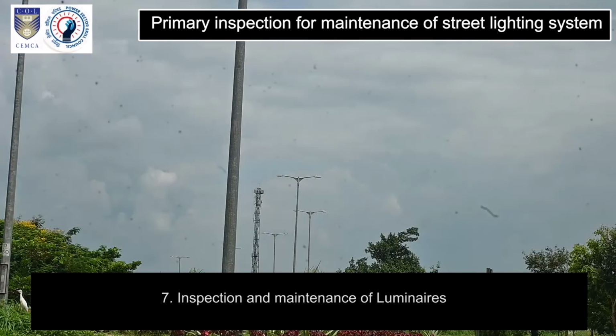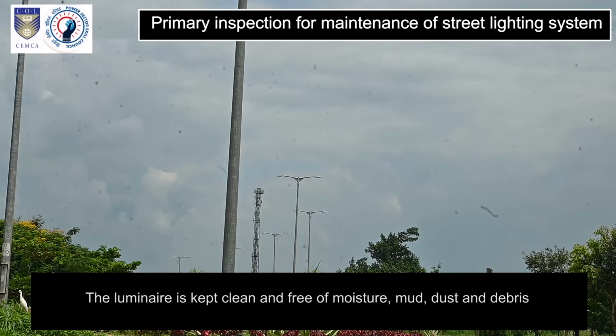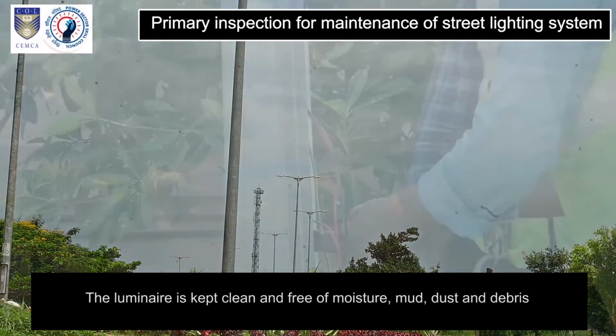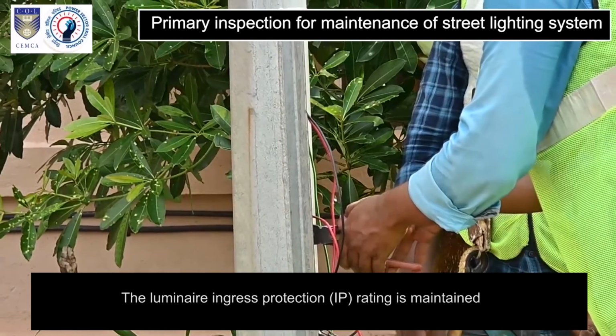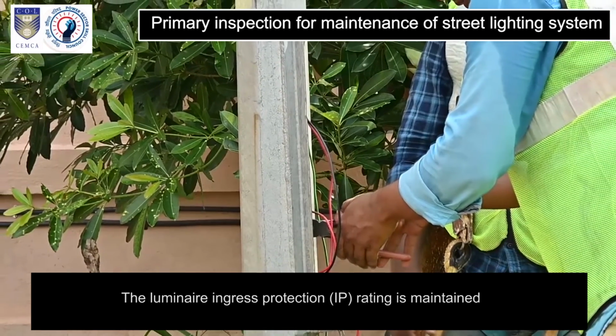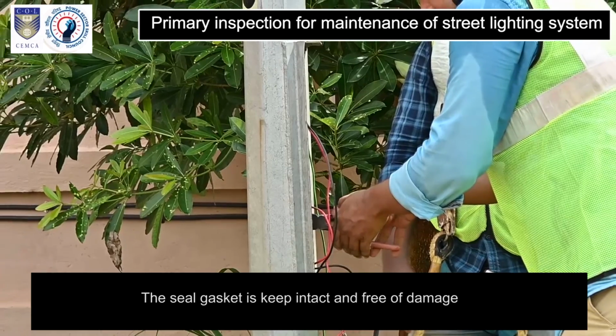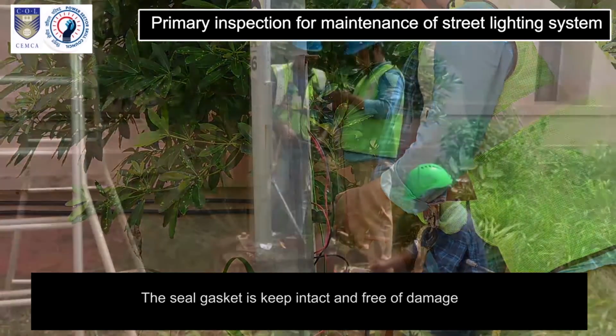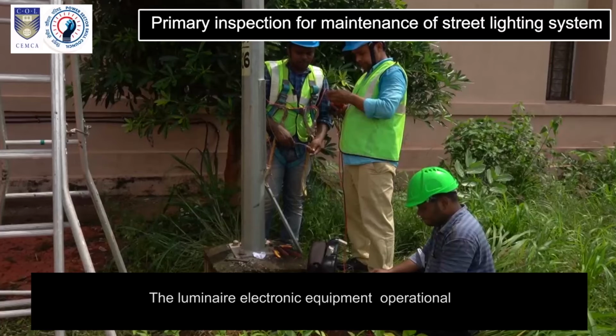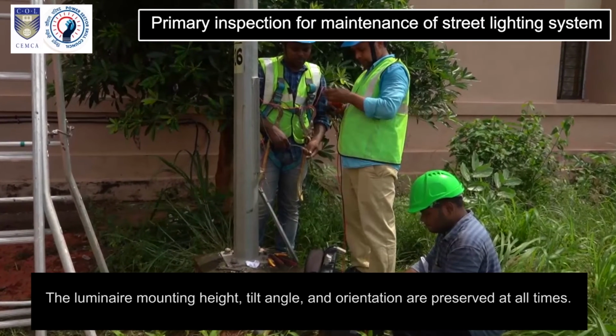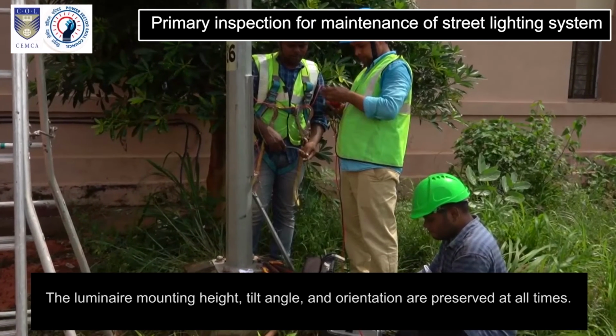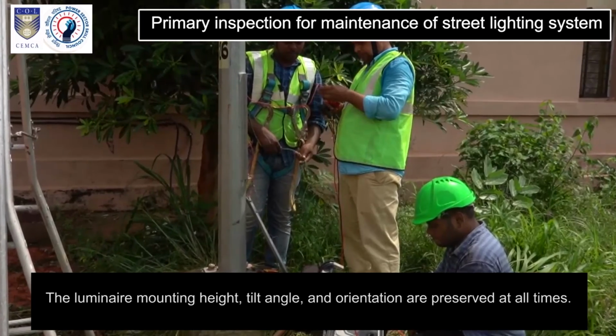7. Inspection and maintenance of luminaires. The luminaire is kept clean and free of moisture, mud, dust, and debris. The luminaire ingress protection IP rating is maintained. The seal gasket is kept intact and free of damage. The luminaire electronic equipment is operational. The luminaire mounting height, tilt angle, and orientation are preserved at all times.